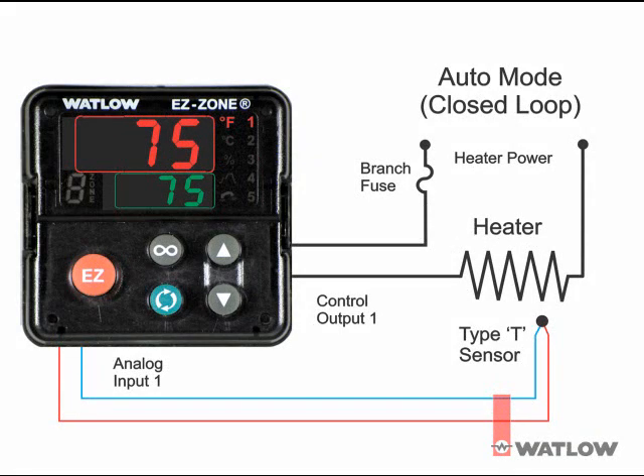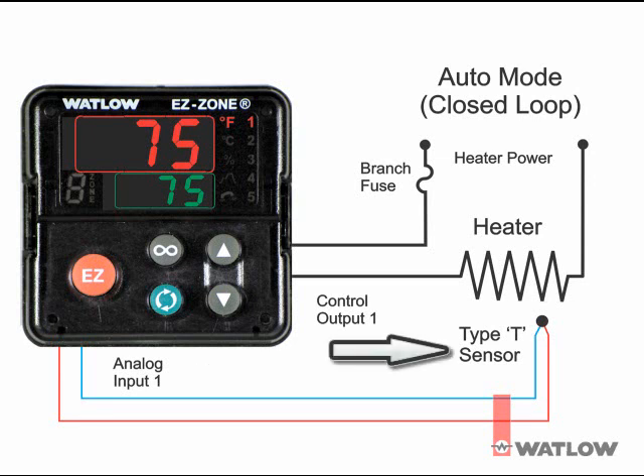In Auto mode, the controller monitors the sensor input to determine if closed loop control is possible. In this diagram, a type T thermocouple monitors the temperature of a heater. The controller checks to make certain a functioning sensor is providing a valid input signal. Assuming the user requested Auto mode and a valid analog input signal is present, the controller will perform closed loop control.